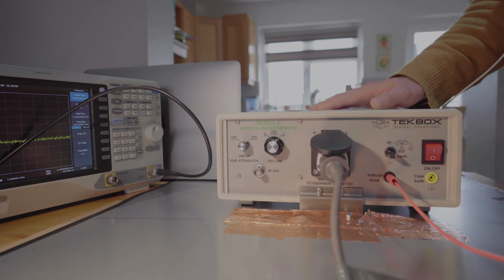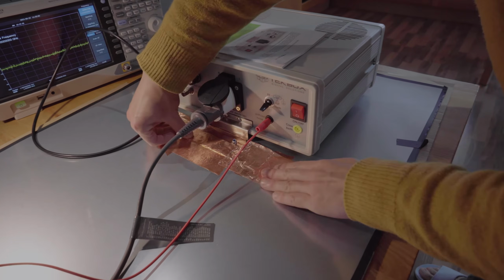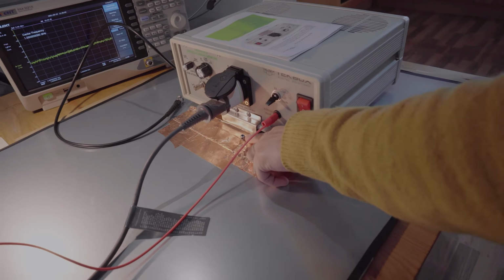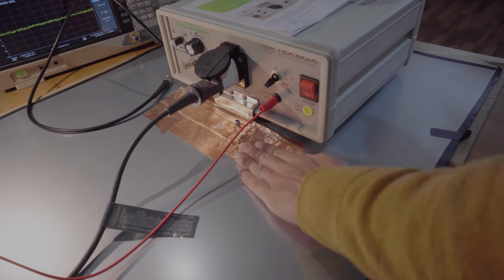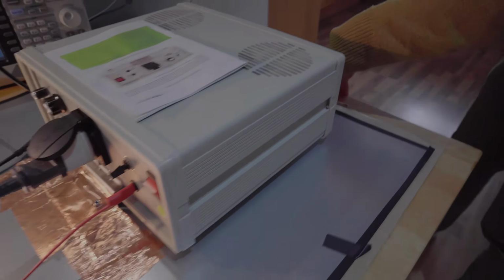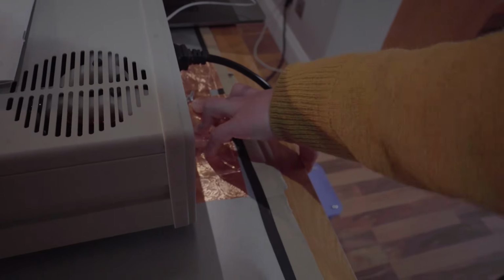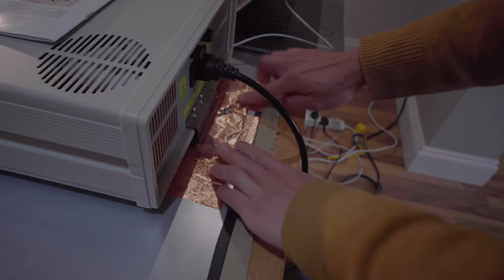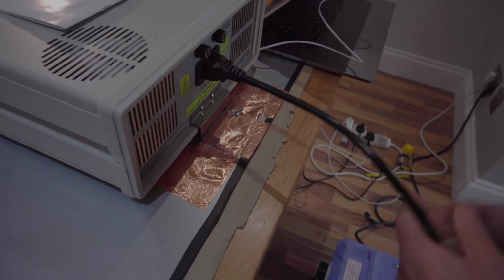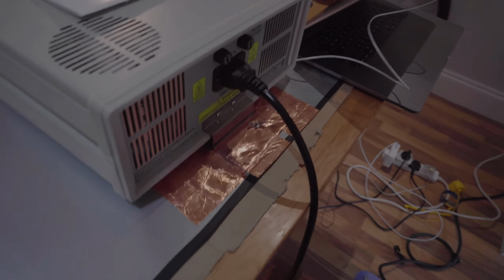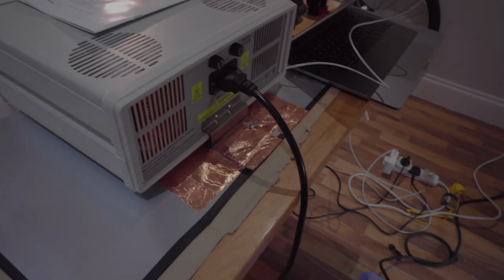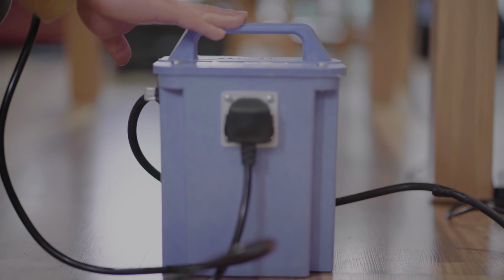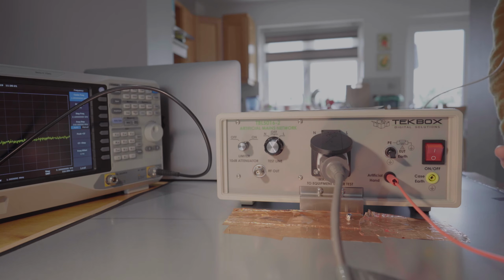So in this case, as you can see, for high voltage safety, you need to bond the LISN front panel securely to the ground plane. Same applies on the rear panel of the LISN, and using copper tape to tape it. And the LISN itself is earthed to the isolation transformer casing, and the transformer itself is earthed. Okay, so make sure that the ground plane is properly earthed.